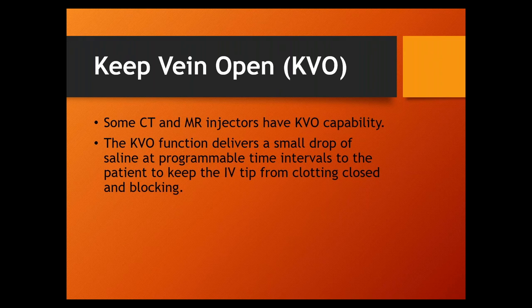KVO stands for Keep Vein Open. Some injector models have this - CT and MRI injectors do; angio injectors don't. CT and MRI injectors use an IV needle, and if you don't shoot fluid through that IV needle for an extended period, a blood clot can start forming at the tip. To prevent this, they program a KVO: a very slow trickle of fluid - typically from the saline syringe - through the end of the IV needle just to keep the vein open. Some models do a constant trickle at 0.1 mL/sec; others do a small shot like 0.25 mL every 20-30 seconds.